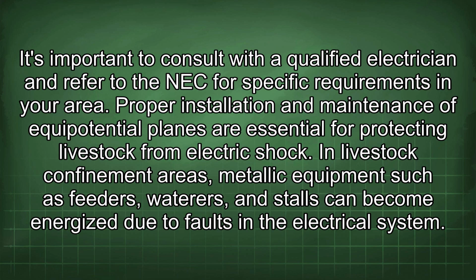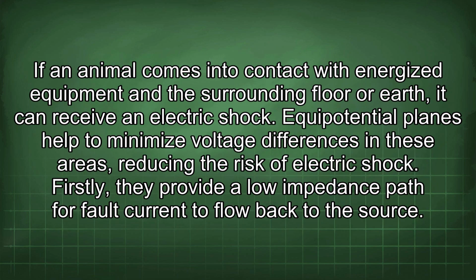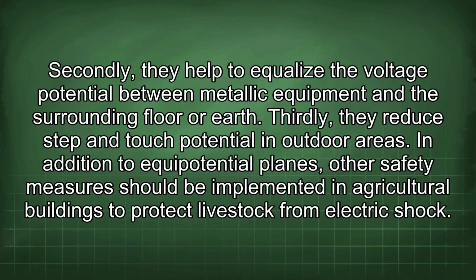In livestock confinement areas, metallic equipment such as feeders, waterers, and stalls can become energized due to faults in the electrical system. If an animal comes into contact with energized equipment and the surrounding floor or earth, it can receive an electric shock. Equipotential planes help to minimize voltage differences in these areas, reducing the risk of electric shock. Firstly, they provide a low impedance path for fault current to flow back to the source. Secondly, they help to equalize the voltage potential between metallic equipment and the surrounding floor or earth. Thirdly, they reduce step and touch potential in outdoor areas.